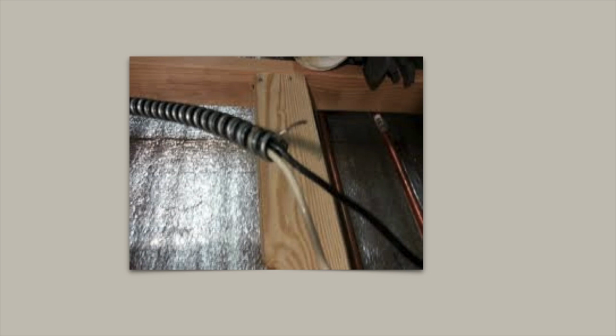Anytime you see a silver-typed wire, look to see how it is jacketed. If it is BX, then you know it is not aluminum. It is tin-clad copper. Years ago, wire manufacturers were coating the copper wire with tin to make it more durable. Do not be fooled into reporting tin-clad copper as aluminum wiring. Determine what jacketing it has and call it out accordingly.